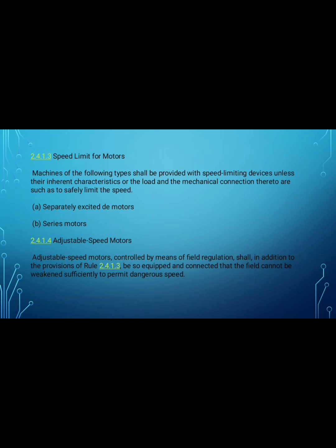2.4.1.3 Speed limit for motors. Machines of the following types shall be provided with speed limiting devices unless their inherent characteristic or the load and the mechanical connection are such as to safely limit the speed: A. Separately excited DC motors. B. Series motors.